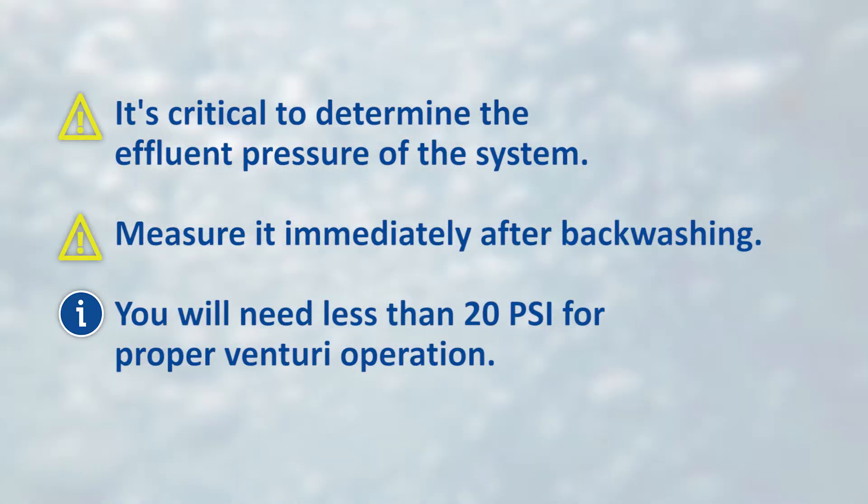It's critical to determine the effluent pressure of the system. Measure it immediately after backwashing when it will be at its highest level. You will typically need less than 20 psi of effluent pressure to allow for proper operation of the venturi.